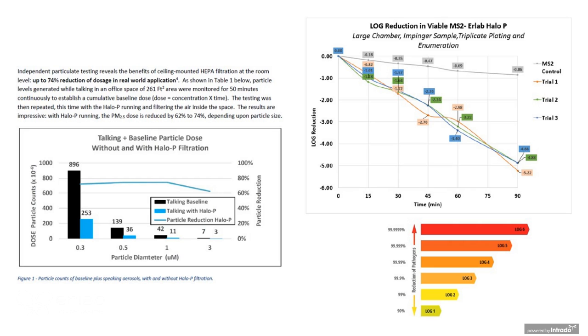So these first graphs are going to show you, the one on the left actually shows a real world scenario in an office space where we wanted to take particle counts when the room itself was active. It's about a 2,700 cubic foot room, and we wanted to take a baseline of the particle counts before. Now this is just particles, these aren't viruses. We then wanted to take a baseline after a ceiling mounted system was installed. And what we saw, at the particles that really matter between 0.3 and 0.5 micron, was 896 million versus 253 million. So we saw a greater than 74% reduction across the board on the smaller particles.